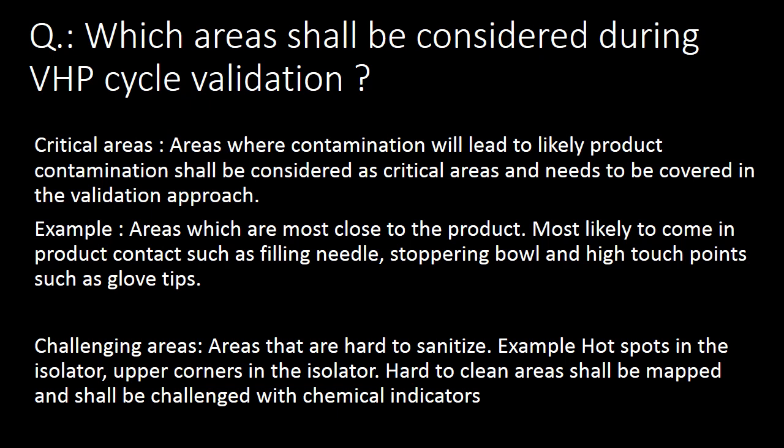Parts most likely to come into product contact — such as filling needles, stoppering bowl, and high touch points such as glove tips — shall be considered as critical areas. For challenging areas, areas that are hard to sanitize, such as hot spots in the isolator and upper corners, shall be considered as challenging areas. Hard-to-clean areas shall be mapped and challenged with chemical indicators.